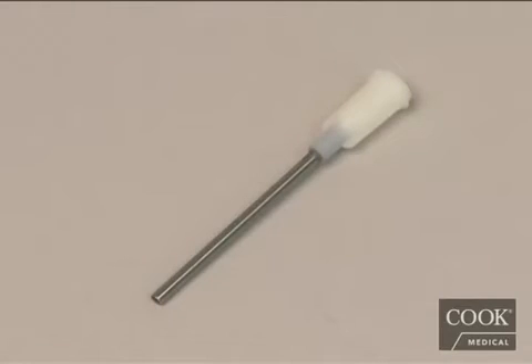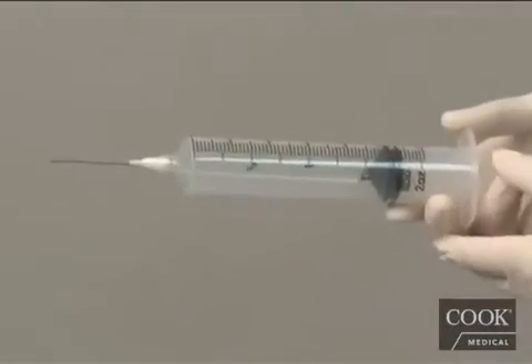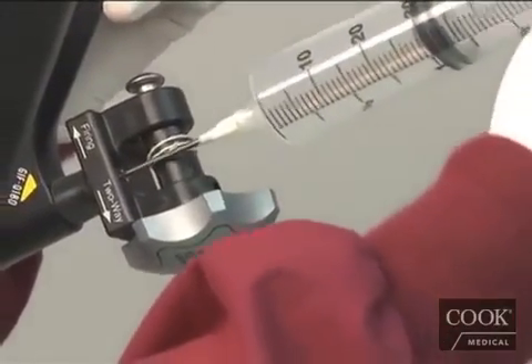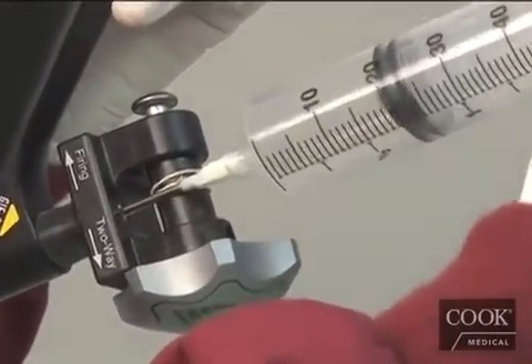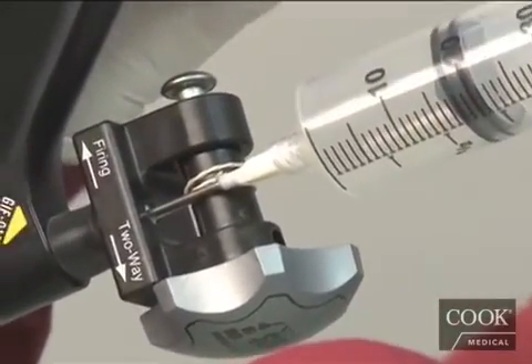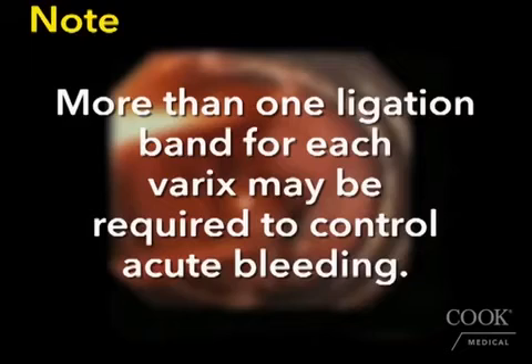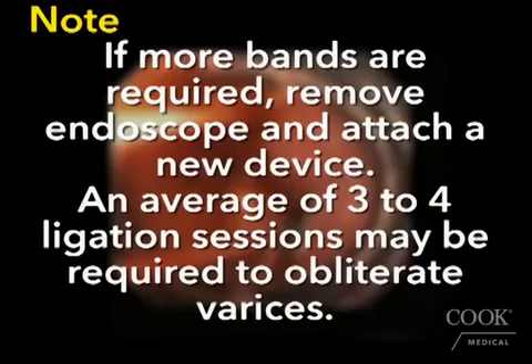Note: an irrigation adapter is provided with each device. If irrigation of the accessory channel is desired to clear the viewing field, attach the adapter to a syringe filled with sterile water and insert into the white seal of the handle. Irrigate as necessary. Repeat the ligation process as needed. Note: more than one ligation band for each varix may be required to control acute bleeding. If more bands are required, remove the endoscope and attach a new device. An average of 3 to 4 ligation sessions may be required to obliterate varices.